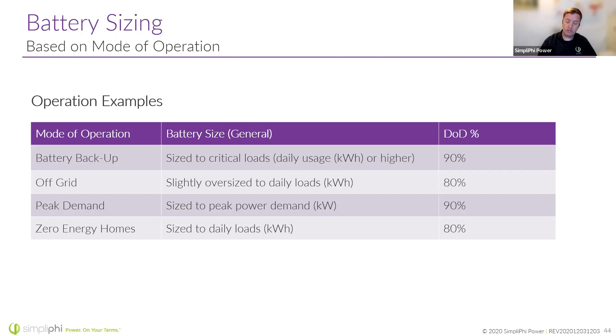When it comes to sizing for power, one thing I really want to be careful to mention, and spend a moment here to talk about, is that the batteries have a C/2 continuous charge or discharge rating. So what this means is, imagine you've got this 8,000 watt Radian sitting here - you want to be sure the batteries are twice the size of the inverter's output capability.